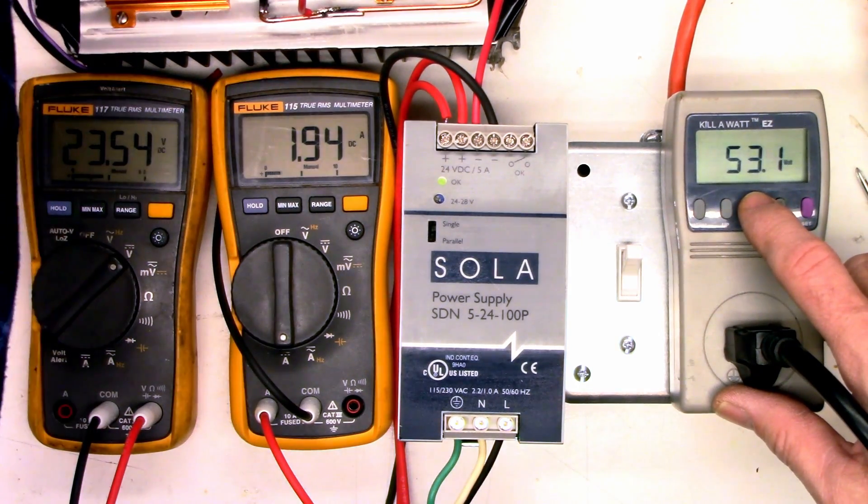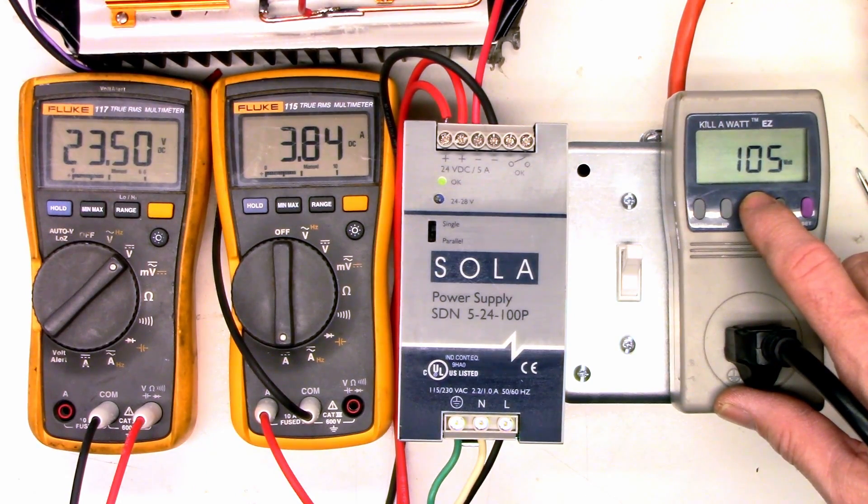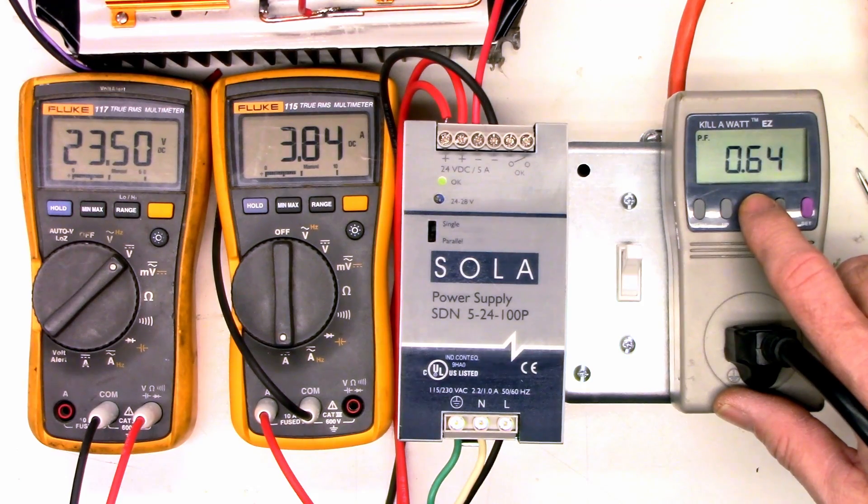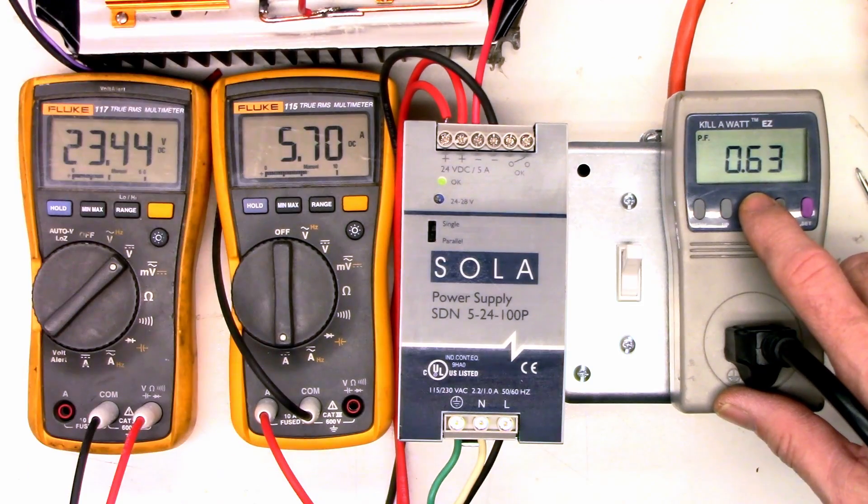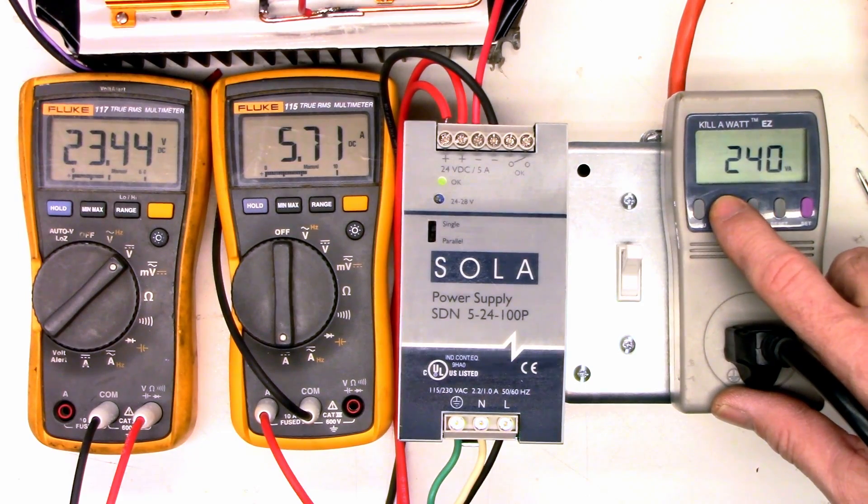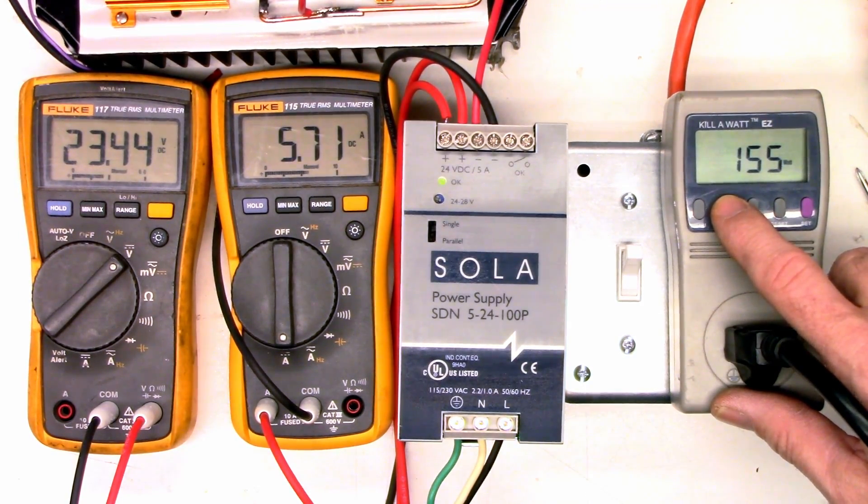Let's turn on the next load. 3.8 amps now. We're up to 105 watts and 161 VA, and our power factor now is 0.64. Seems pretty constant. Next load, 5.7 amps. Power factor went to 0.65 now. Our VA is now 240, and our watts is now 155.